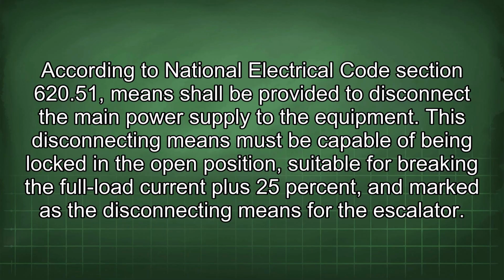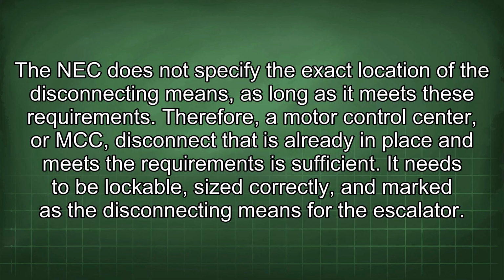According to National Electrical Code Section 620.51, means shall be provided to disconnect the main power supply to the equipment. This disconnecting means must be capable of being locked in the open position, suitable for breaking the full load current plus 25%, and marked as the disconnecting means for the escalator. The NEC does not specify the exact location of the disconnecting means as long as it meets these requirements.